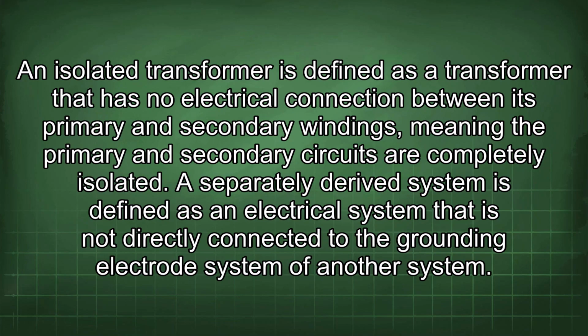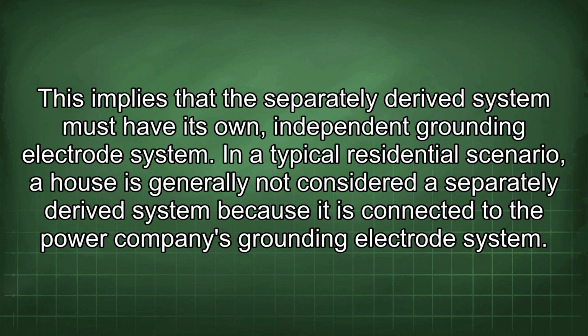An isolated transformer is defined as a transformer that has no electrical connection between its primary and secondary windings, meaning the primary and secondary circuits are completely isolated. A separately derived system is defined as an electrical system that is not directly connected to the grounding electrode system of another system. This implies that the separately derived system must have its own independent grounding electrode system.